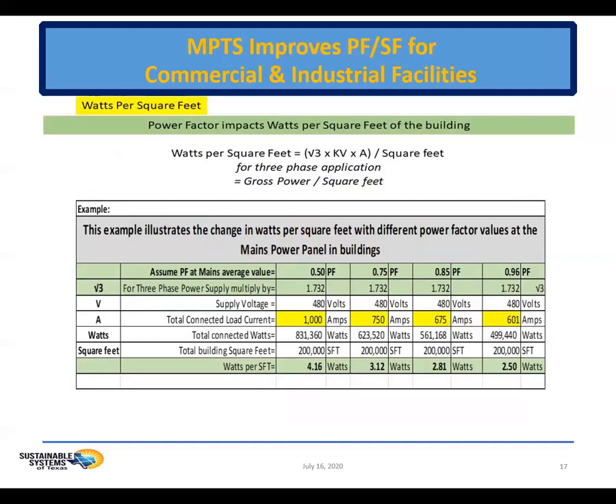As you can see, when your power factor is low at 0.50 and your total connected load would be 1,000 amps, your watts per square foot would be 4.16. But as you improve your power factor all the way to 0.96, your amps decrease to 601 amps, and your watts per square foot decrease to 2.5. That's almost a 50% savings in your power consumption at your facility.